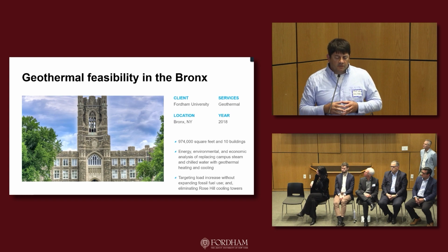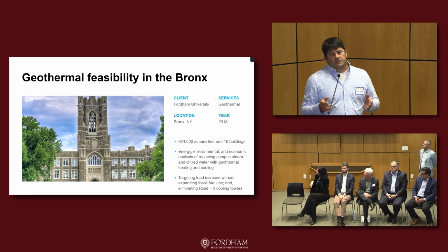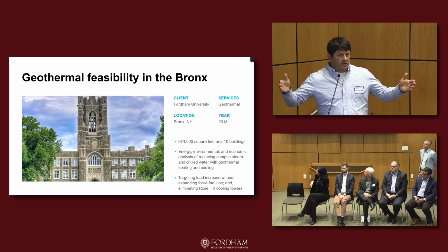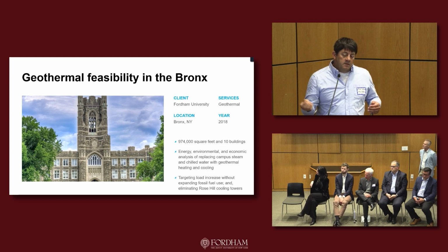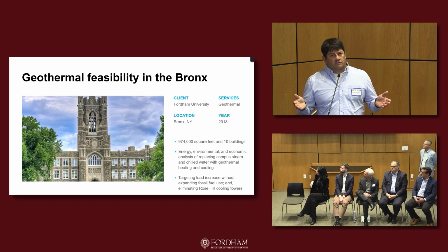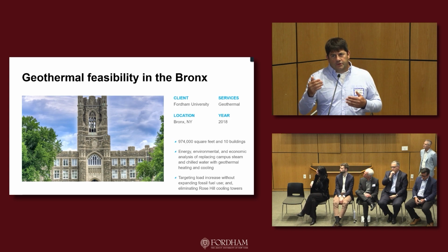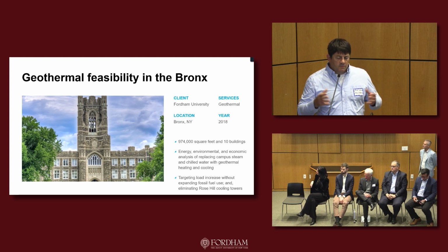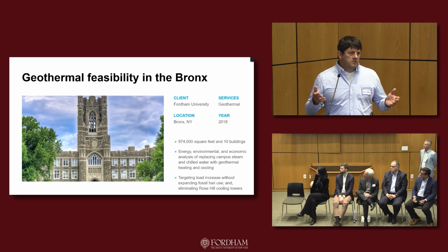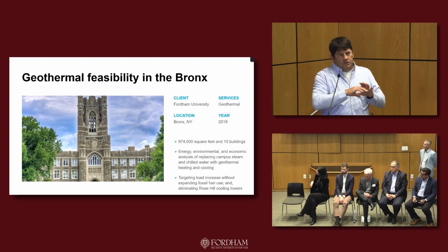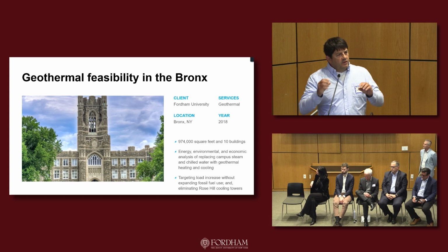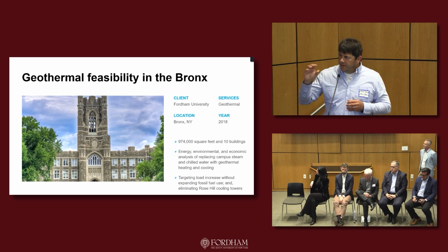It could be a recip type compressor, a screw compressor, whatever it may be, to give us that extra lift that we need. And the key there is you don't jeopardize your whole campus, right? Your plant doesn't take the whole hit to make that higher water temperature. Especially at Fordham, a lot of their buildings are 2-pipe switchovers. They've already been set up for a low water temperature campus distribution. They can easily heat their buildings probably with 110-degree water because with the switchover, they're all cooling coils in the fan coil units. 4-row, 6-row coils, perfect for a low water temperature. So we don't want to jeopardize our high-efficiency new plant for just a few outlying buildings. You're best then to put in some spot high-temperature lift heat pumps, pick those buildings up.